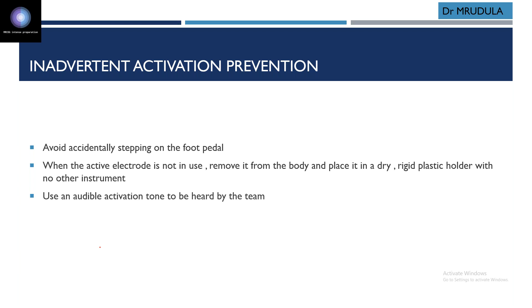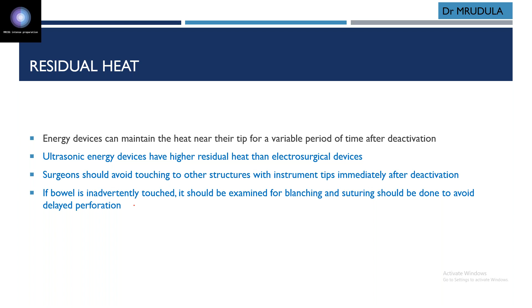Coming to residual heat. Energy devices can maintain heat near the tip for a variable period of time after deactivation. Ultrasonic energy devices have higher residual heat than electrosurgical devices. We think that harmonic devices will have low residual heat, but no, they have higher residual heat. The surgeon should avoid touching other instruments or tissue with the instrument tip immediately after deactivation, because the residual heat may get transferred to other areas. If the bowel is inadvertently touched, it should be examined for blanching, and suturing should be done to avoid delayed perforation. This again, I think I have read in some question somewhere. So what happens if you inadvertently touch the bowel? Look for blanching. If blanching is present, suture it.